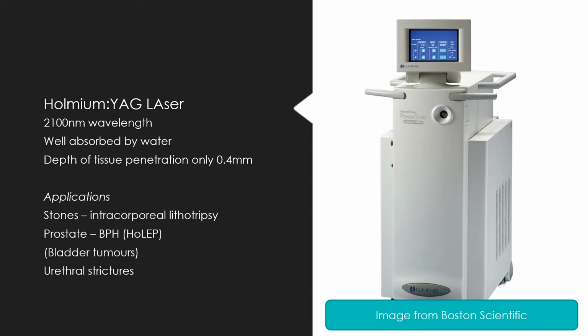These plasma bubbles expand and collapse, giving rise to acoustic shock waves, which may further damage the stone. It is thought, however, that this photoacoustic effect is less important as far as the Holmium YAG laser goes, and most of the stone disruption is by the photothermal effect.